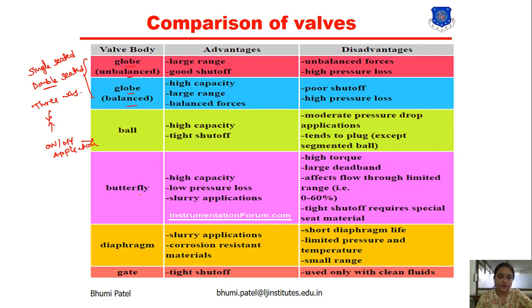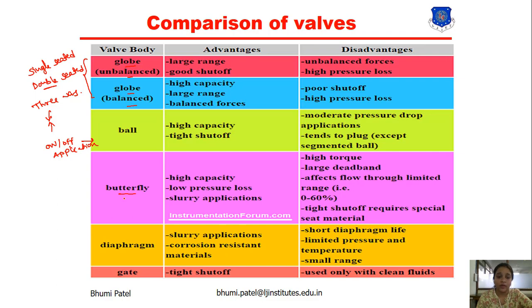The butterfly valve has a similar construction to the ball valve. It is used for high capacity, low pressure drop, and its main application is slurry service. The disadvantage is it requires high torque, has a large dead band, and affects flow through a limited range of 0 to 60 percent. Tight shutoff requires special seat material, so for special applications a special butterfly valve material must be used.